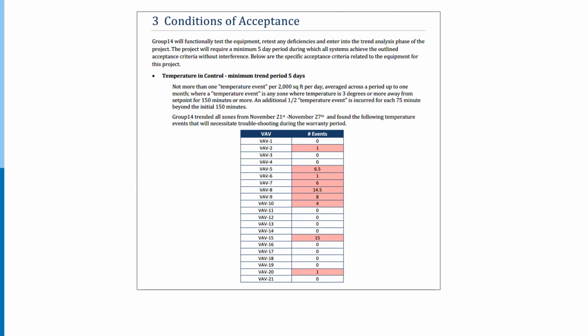First things first, we always want to see temperature in control. So nowadays we've simplified this to just ask for plus or minus 3 degrees of set point for 90% of observations. But for this test, we use this definition of a comfort event, right? One comfort event is when the zone is more than 3 degrees out of set point for more than about 2.5 hours. And as you can see, over a 6-day trending period, we do have a bunch of zones here that really aren't in very good control, right?